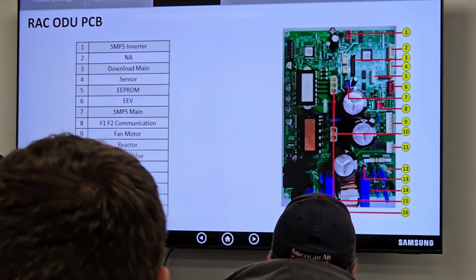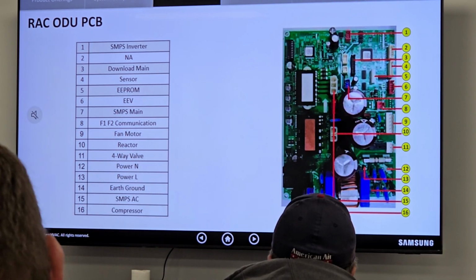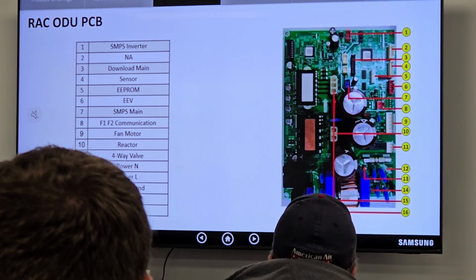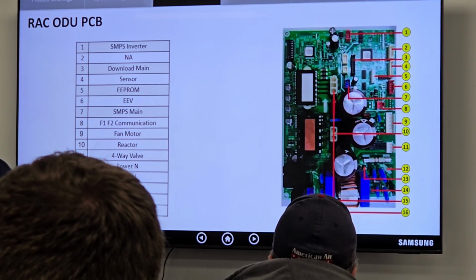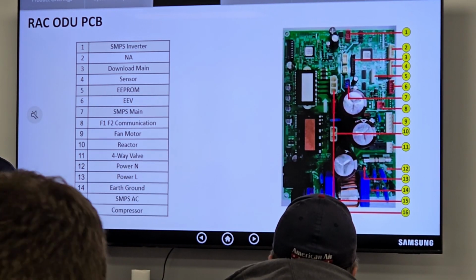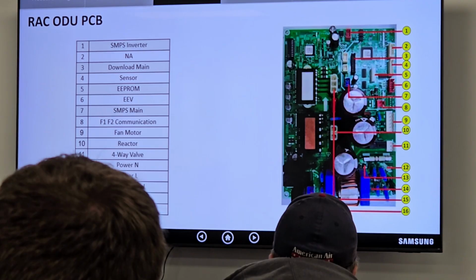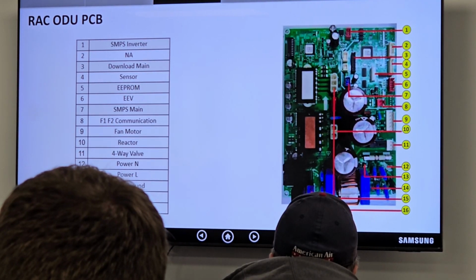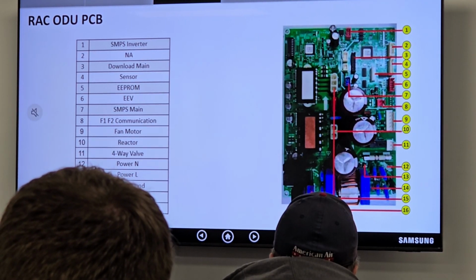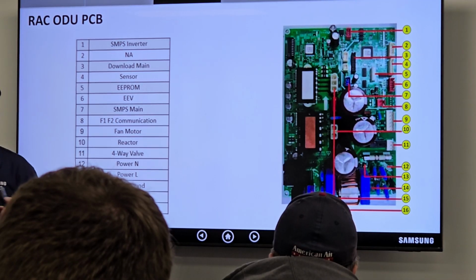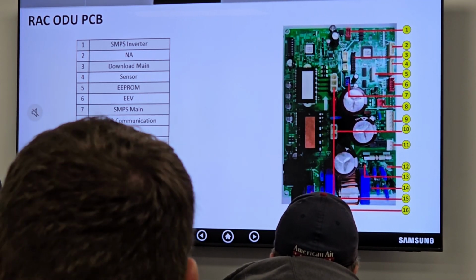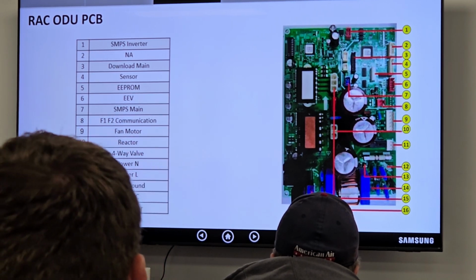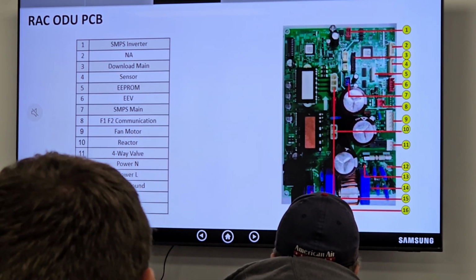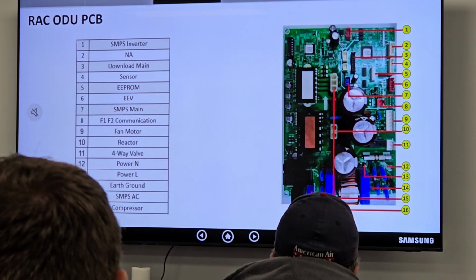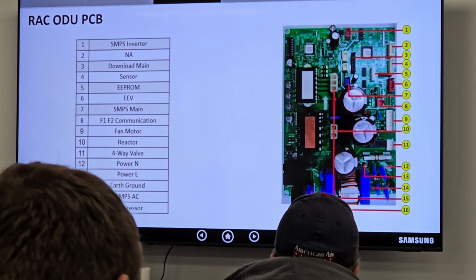If you think about it, and I know this is going off in a different direction, most of your commercial products are energized in heat. A lot of commercial products in the 80s and 90s used a conventional setup: W1 energized the relay, which energized the compressor contactor, and energized the reversing valve. Why do you think we do that? So you would have air, you'd always have air, and you have electric strips for heat. So most people can get warm, you just can't get cool.